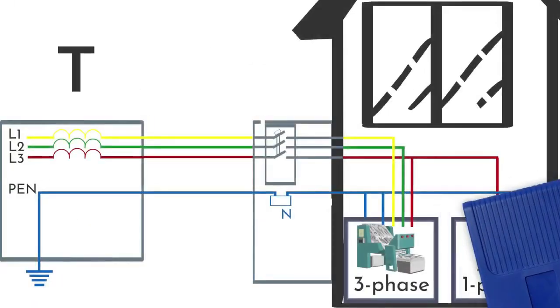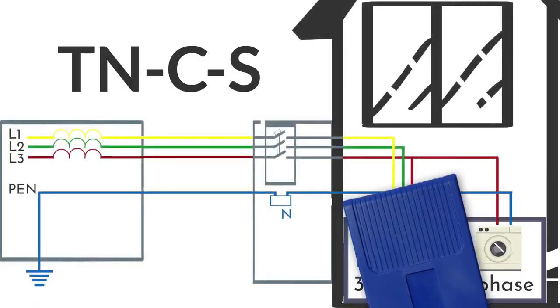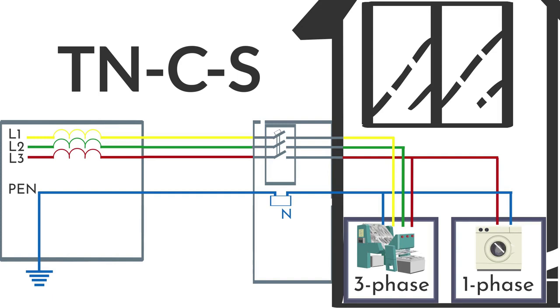Now let's talk about the TN-CS grounding system. At the moment, it is a very common power supply system. Just like in the previous case, its neutral conductor is solidly grounded in the transformer substation. The PEN conductor in the input device is divided into zero working and zero protective conductors. Furthermore, the PE bus is grounded once again.